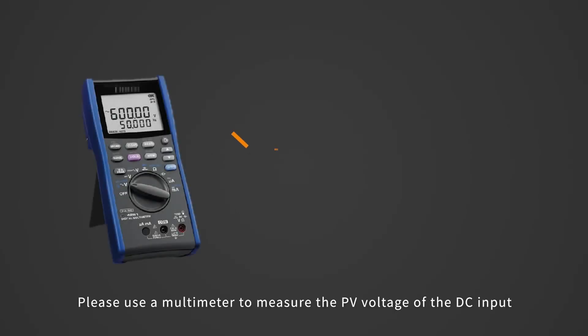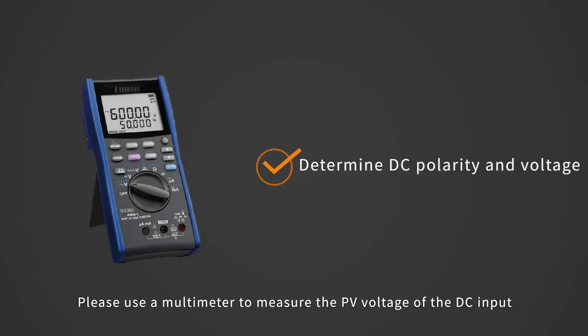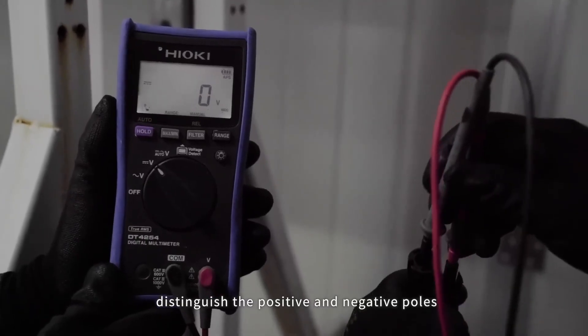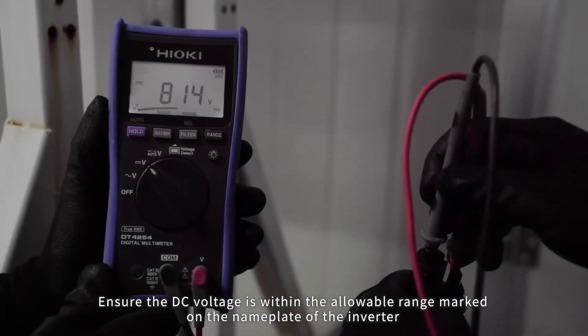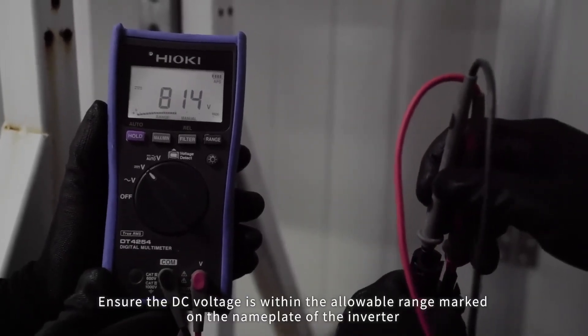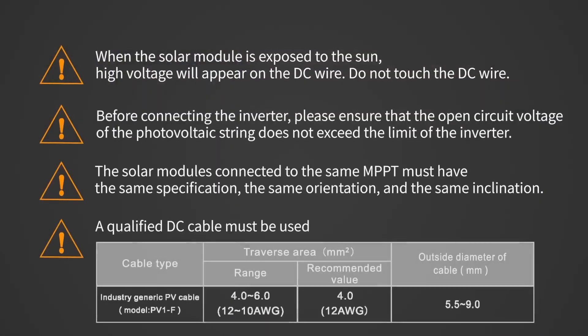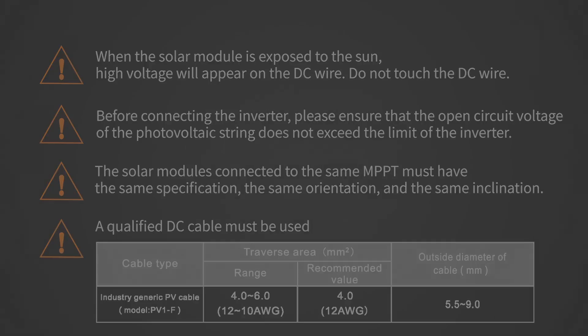DC side connection. Please use a multimeter to measure the PV voltage of the DC input and distinguish the positive and negative poles. Ensure the DC voltage is within the allowable range marked on the nameplate of the inverter. Please refer to Solis's demonstration video for making a DC connection cable.